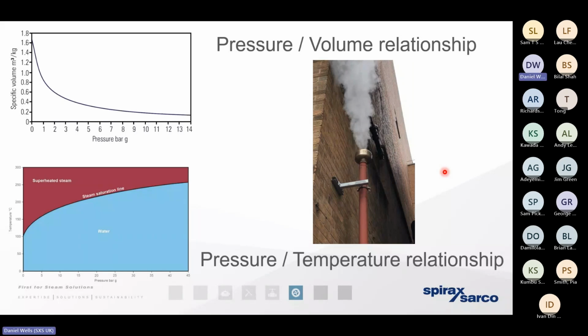So as that condensate depressurizes, a certain mass, a certain volume's got to boil off, change state from a liquid back to steam as a gas again, and it's going to expand to a significant factor, maybe as high as 1,600 times greater in volume than when that condensate exists as a single phase liquid. And the pipework downstream of the steam trap, that's been sized to accommodate condensate as a liquid. So it can't contain that expansion. We've got to vent it away to protect the infrastructure from any damage.